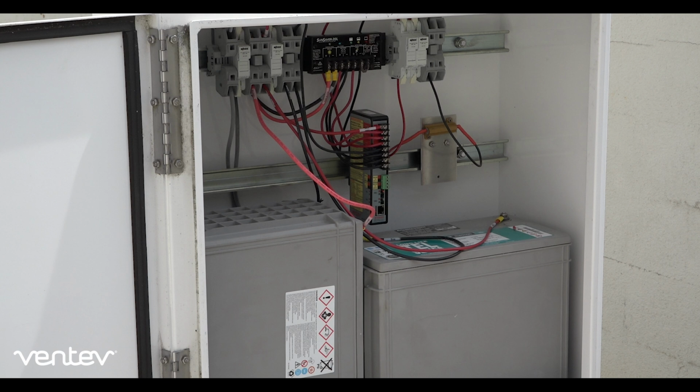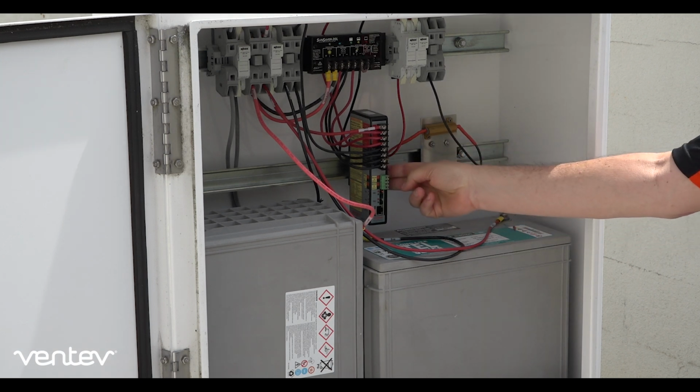That's awesome. It brings up an interesting question, though, in terms of the batteries, Jim, and I notice a device sitting in there. These are often deployed in some pretty remote areas or somewhere I may not be walking by and checking them on a regular basis, and of course batteries over time degrade. How do I monitor them to ensure that they're functioning correctly without actually having to roll a truck into the middle of nowhere? Okay, we have this device that you were referring to, which is the BTRM 300.